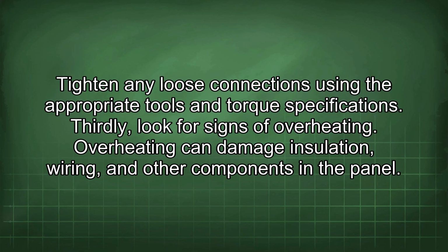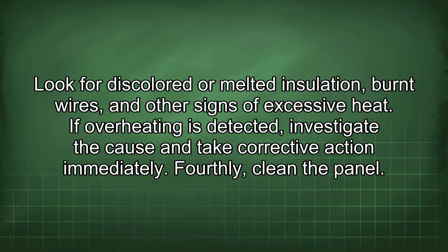Thirdly, look for signs of overheating. Overheating can damage insulation, wiring, and other components in the panel. Look for discolored or melted insulation, burnt wires, and other signs of excessive heat. If overheating is detected, investigate the cause and take corrective action immediately.